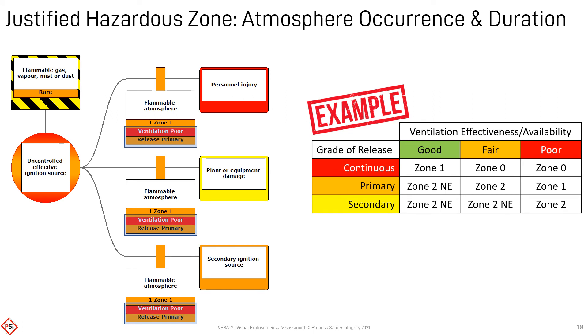The potential for a flammable atmosphere may already be known as part of a hazardous area classification. Otherwise it may be predicted using simple principles, such as the grade of release and the effectiveness and availability of ventilation. This example is a modified EN60079 Part 10.1 approach; however, alternative approaches may be used according to your jurisdiction or company standards.